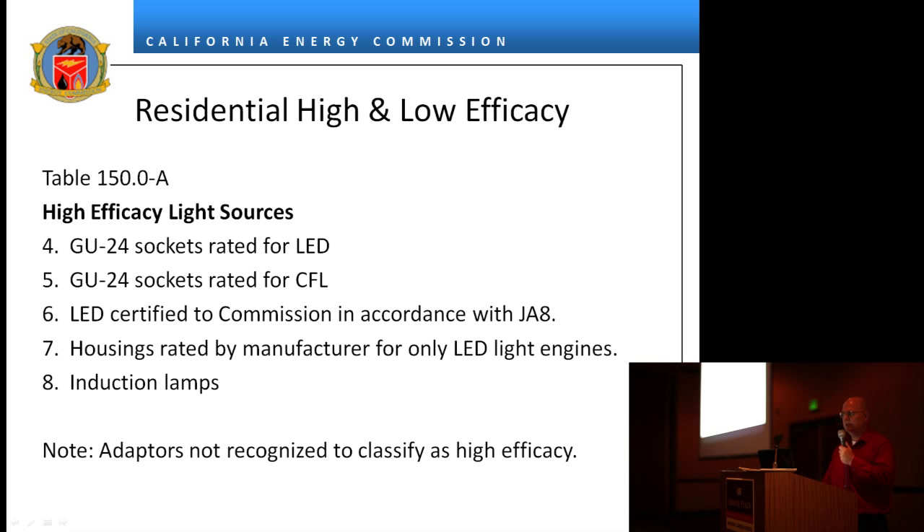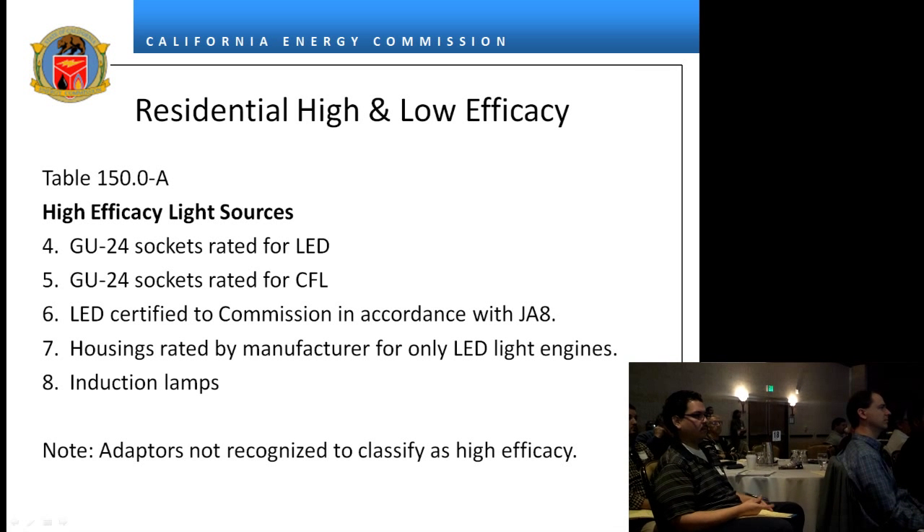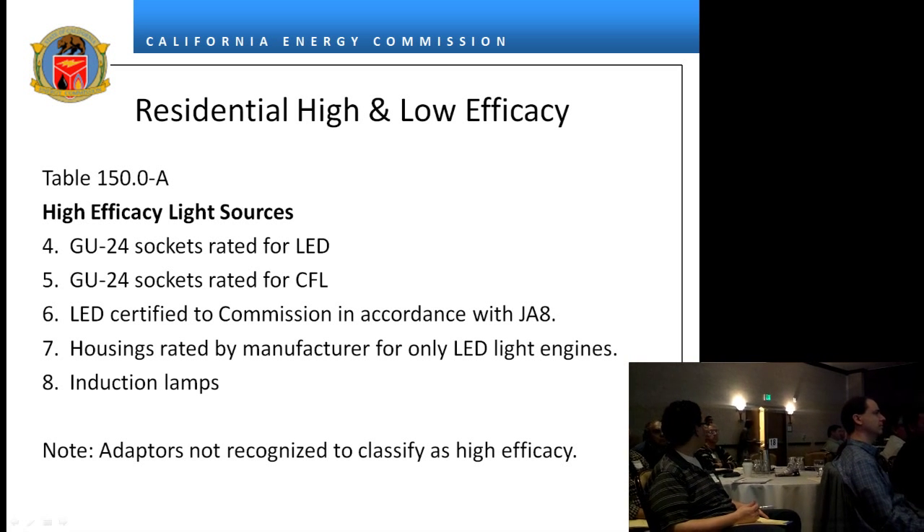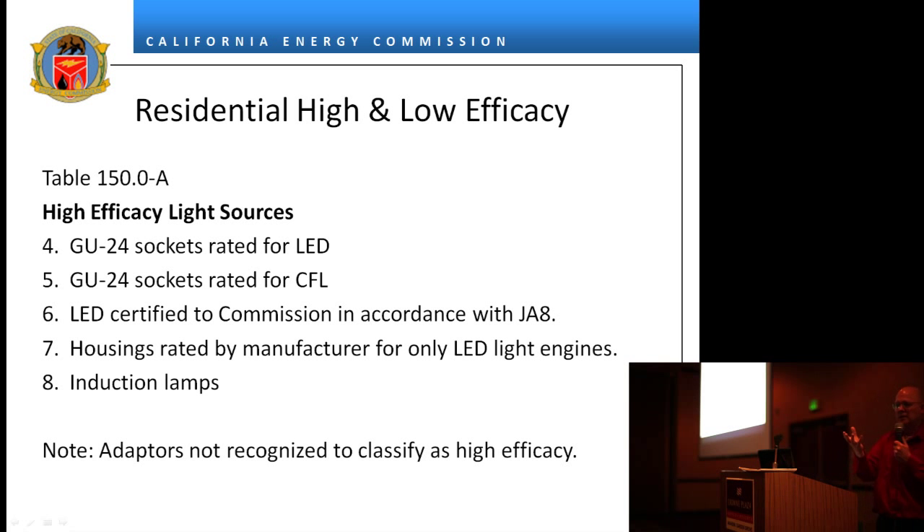For LED, a luminaire would be certified to the commission as high efficacy according to JA8. Housing rated for only LED and induction lamps qualifies. If you take a housing with nothing in it but a GU24 socket and the housing is rated for LEDs, the engine is expected to be in place before the building inspector signs off. Even though the standards say a housing with a GU24 socket and an LED label is an LED luminaire, the engine has to be in place before it gets signed off by the building inspector.